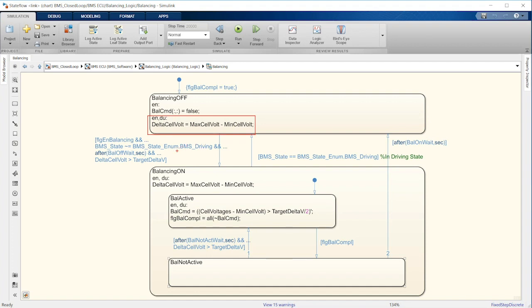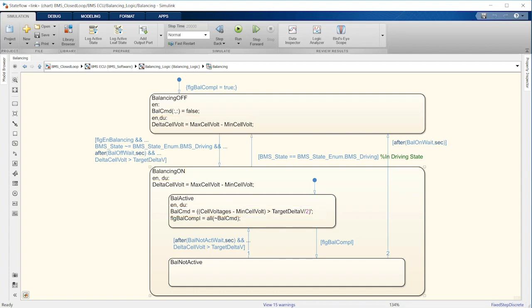The balance command is a Boolean vector that indicates which bleed resistor to activate so that the cell SOC is slowly reduced. Doing this with all cells but the one whose SOC is the lowest eventually makes all SOCs converge within a prescribed tolerance.